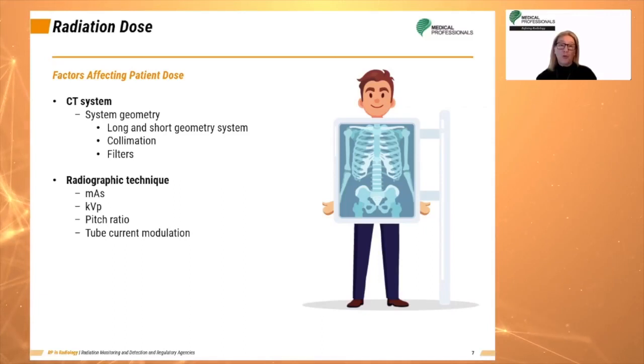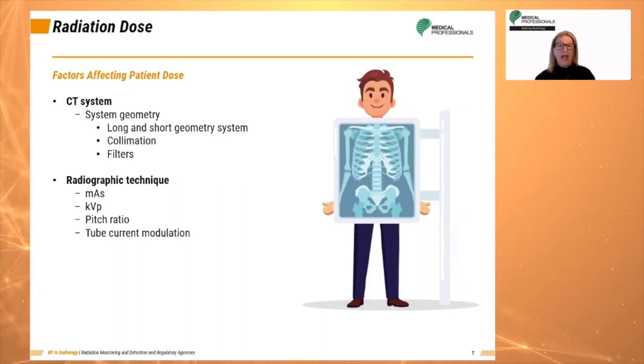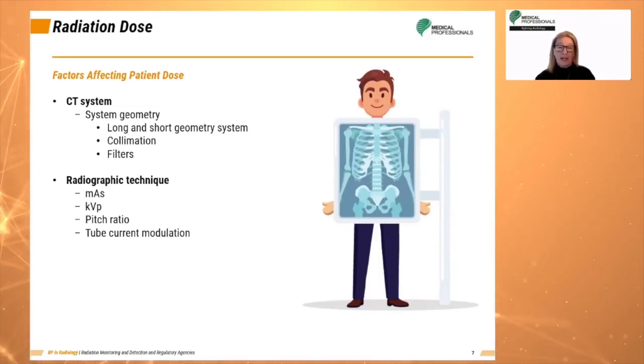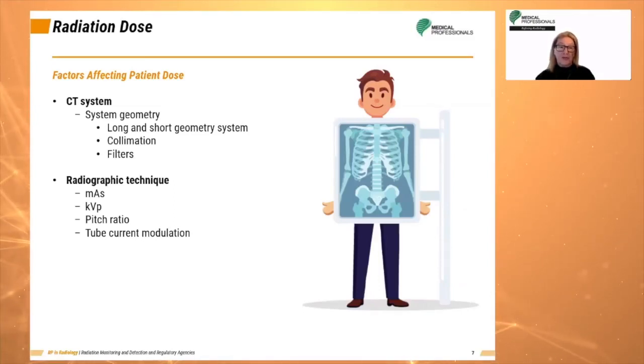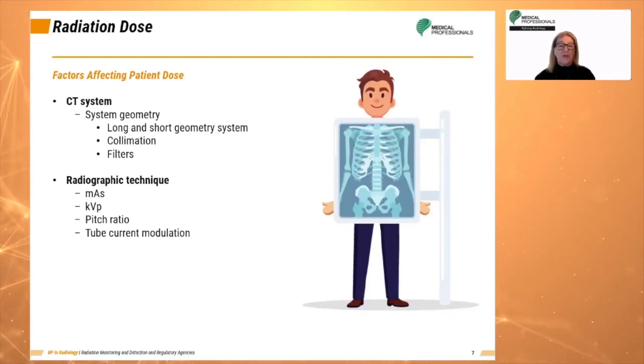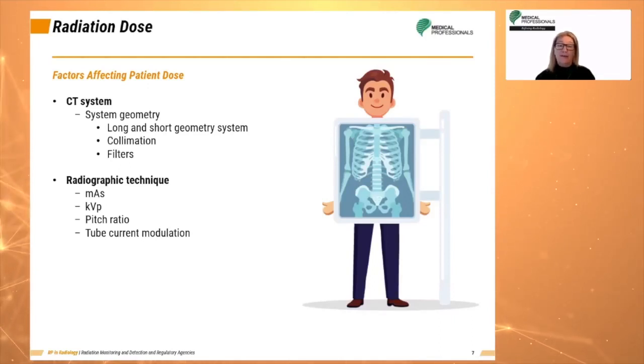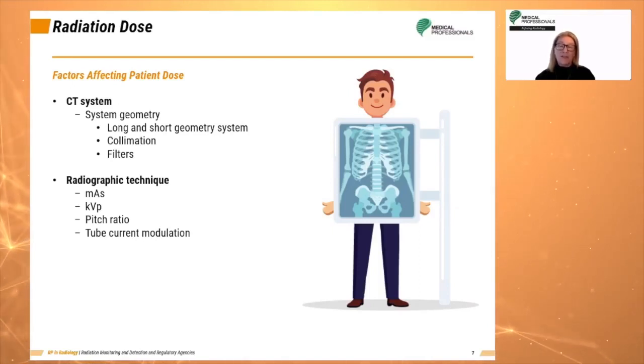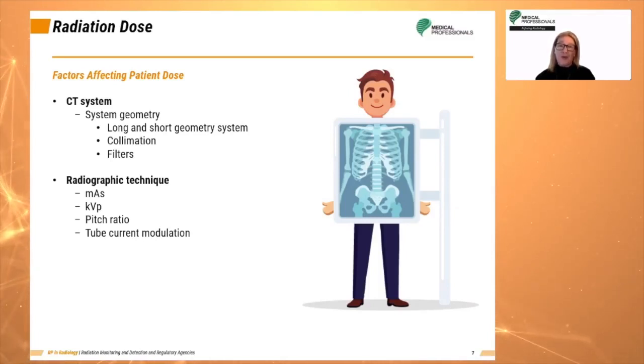Filters are added material that increases the effective x-ray energy by absorbing low-energy x-rays. These are designed to reduce patient dose. Collimators restrict the useful x-ray beam to the anatomical area of interest. Their main purpose is to reduce patient dose and improve image quality.